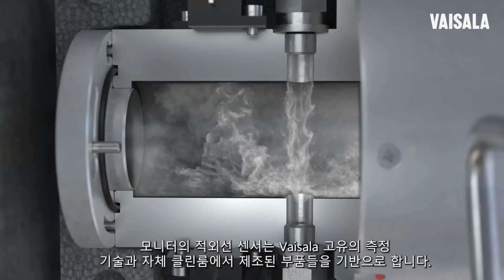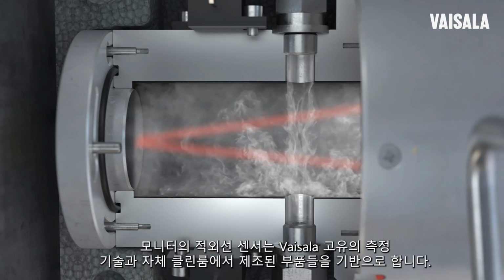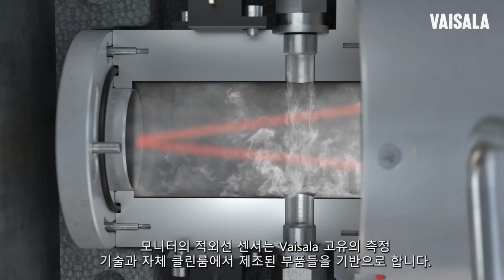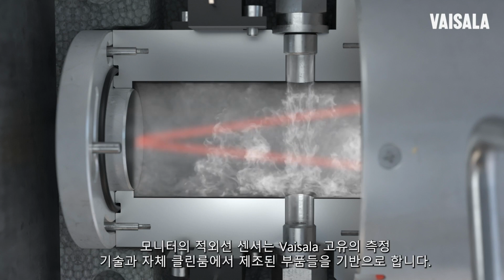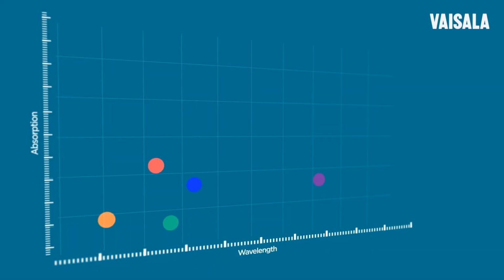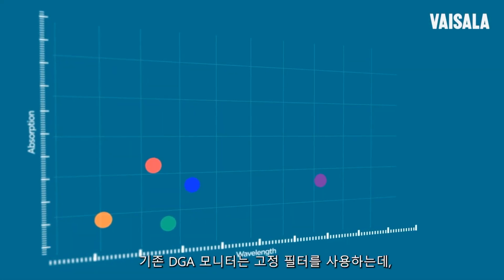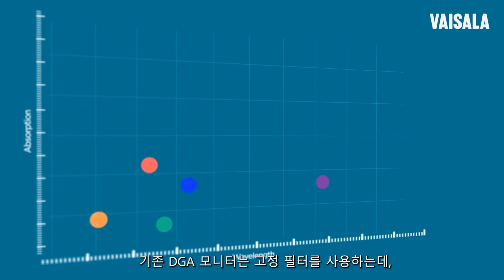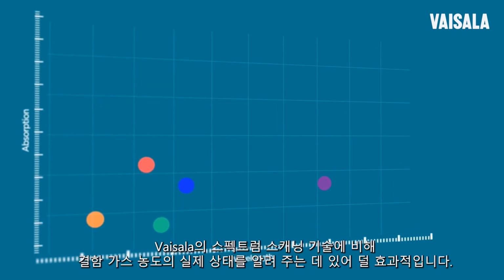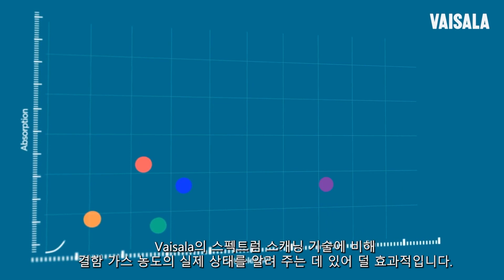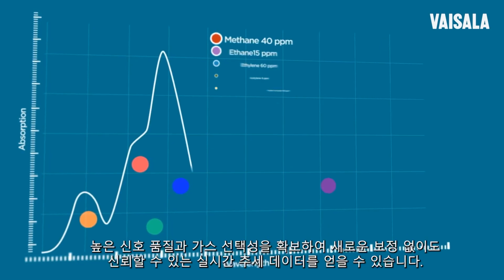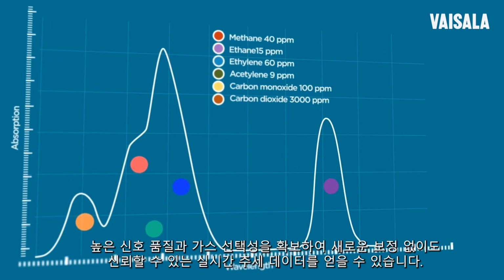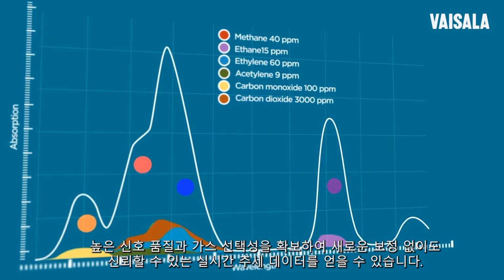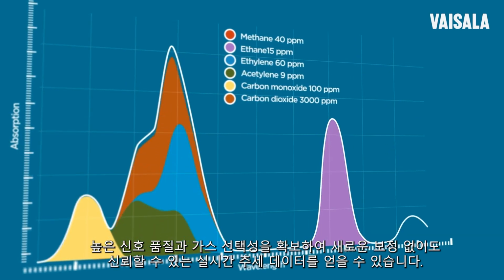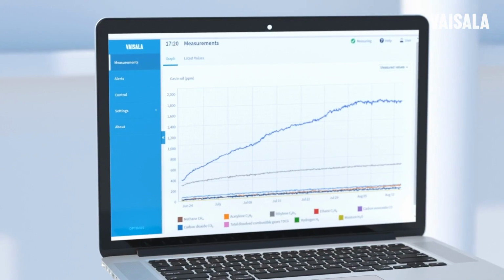The monitor's infrared sensor is based on Vaisala's unique measurement technology and components manufactured in our own clean rooms. Traditional DGA monitors use fixed filters, which are less effective at giving the true state of fault gas concentrations than Vaisala technology with spectral scanning. You get high signal quality and gas selectivity, resulting in dependable, real-time trend data with no need for new calibrations.